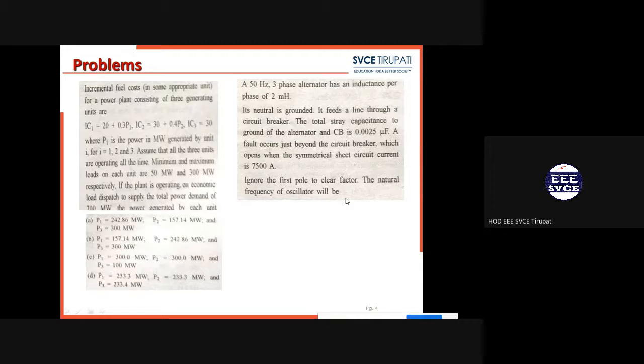If you read all this data, you will get more confused. Why? Because they say there is an alternator and a circuit breaker. The purpose of the circuit breaker is to protect the alternator, so it will trip whenever there is a fault, immediately tripping and not allowing high currents into the machine, protecting the winding of the machine.